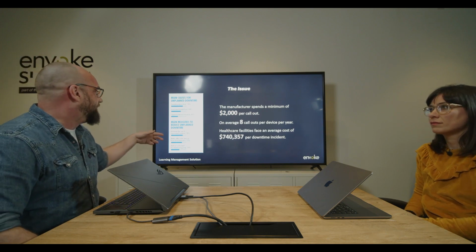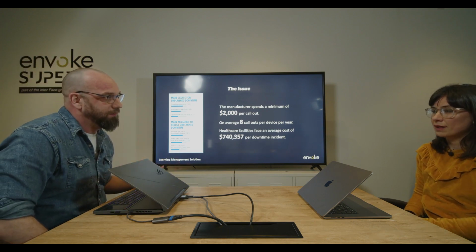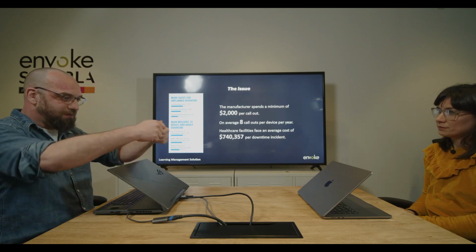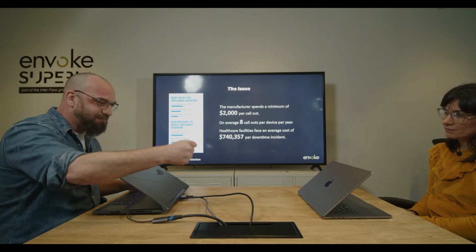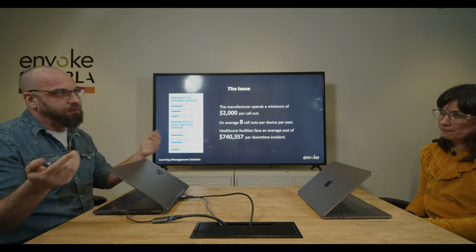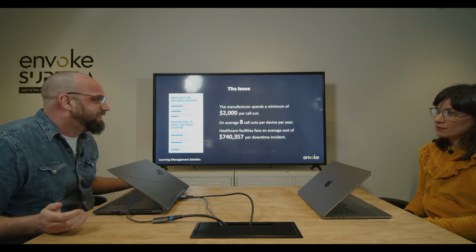Operator technician error. So the person just didn't know how to use the machine properly. They've got the sample prep right, they've put it into the machine right, and then they press the wrong button and it's done the wrong thing. So that's the reason these things are breaking.